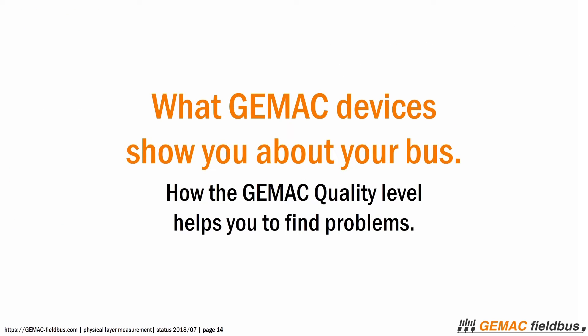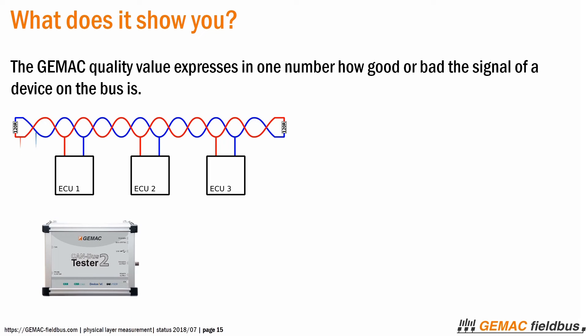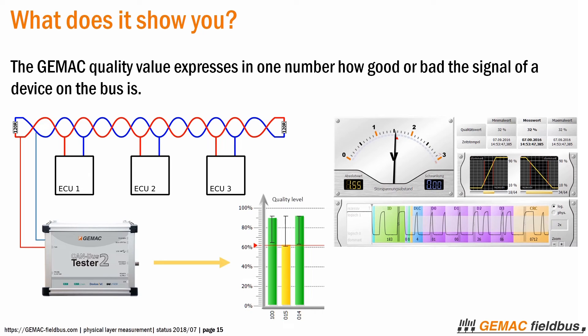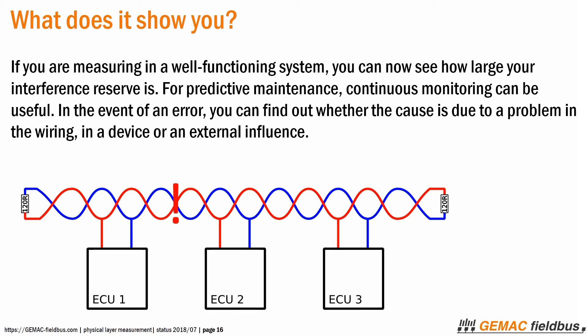What GEMAC devices show you about your bus, and how the GEMAC quality level helps you find problems. The GEMAC quality value expresses in one number how good or bad the signal of a device in the bus is. If you are measuring in a well-functioning system, you can now see how large your interference reserve is. For predictive maintenance, continuous monitoring can be useful. In the event of an error, you can find out whether the cause is due to a problem in the wiring, in a device, or an external influence.